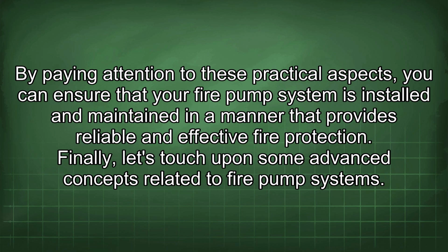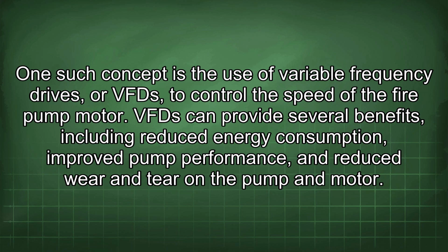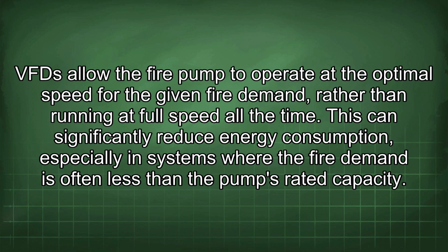By paying attention to these practical aspects, you can ensure that your fire pump system is installed and maintained in a manner that provides reliable and effective fire protection. Finally, let's touch upon some advanced concepts related to fire pump systems. One such concept is the use of variable frequency drives, or VFDs, to control the speed of the fire pump motor. VFDs can provide several benefits, including reduced energy consumption, improved pump performance, and reduced wear and tear on the pump and motor. VFDs allow the fire pump to operate at the optimal speed for the given fire demand, rather than running at full speed all the time.